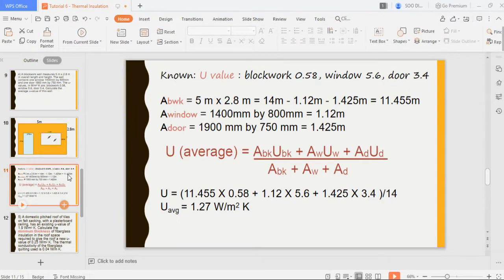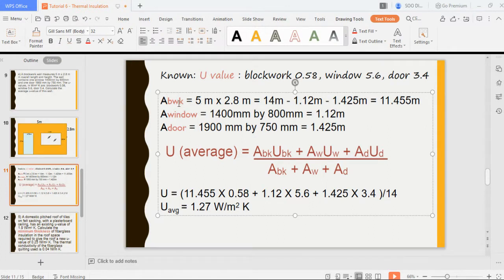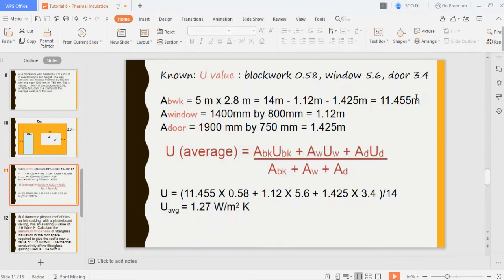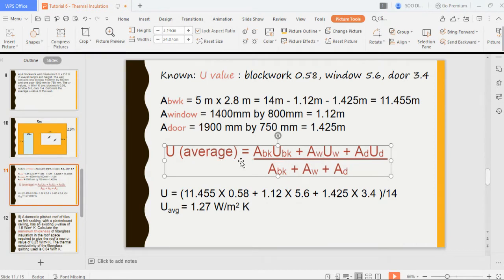First, find the area of each component. The blockwork area is 5 times 2.8 minus the window and door areas, giving 11.45 m². Window area is 1.12 m² and door area is 1.42 m². Then use the average U-value formula — multiply each U-value by its area and sum them — to get an average U-value of 1.27 W/m²K. This formula should be familiar from Topic 2.